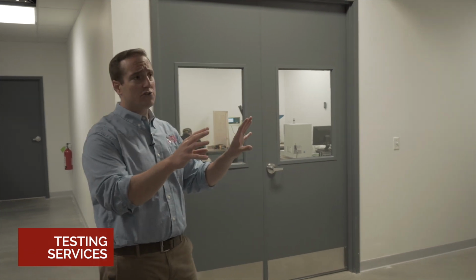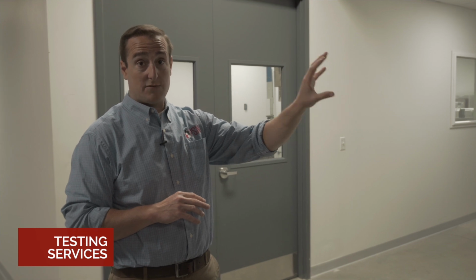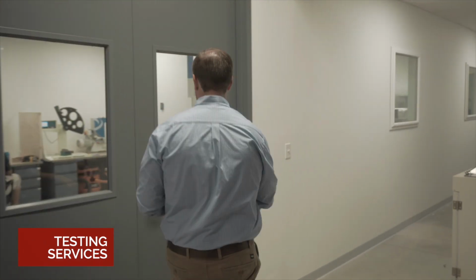I will mention also that this lab, per ISO 17025, is on a backup generator, so that if we're in the middle of running one of our tests for our clients and we have a disruption, there is no disruption to the test that's actually running. This room has its own separate HVAC system, has its own separate room to run gases and fluids as needed, so that we can, from a safety perspective, kind of isolate anything that might be questionable.